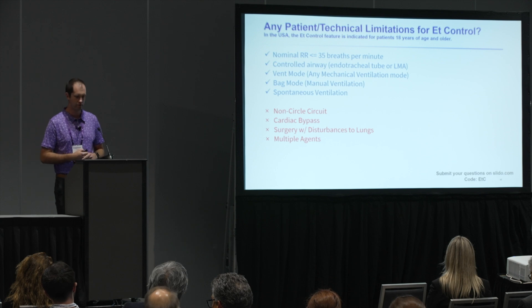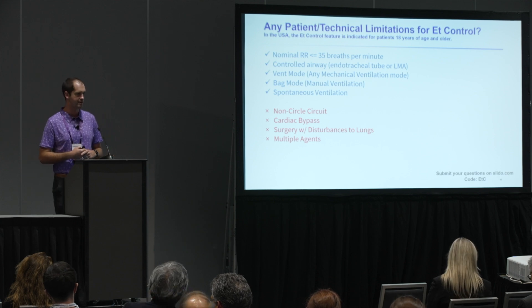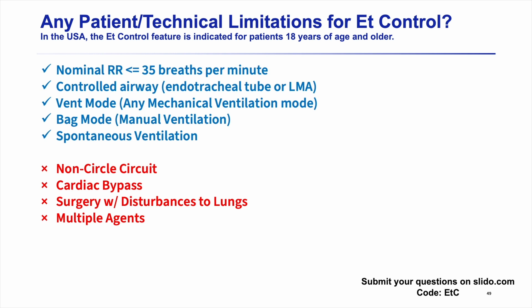What patients can you actually use end-tidal control on? It is indicated for patients 18 years of age or older in the US. You'll need RR less than 35 and a controlled airway. You can use it in any mechanical ventilation mode, in bag mode, or spontaneous ventilation — a pretty wide array of patients. Cases you can't use it on: non-circle circuit, cardiac bypass, surgeries that will have disturbances to the lungs or big leaks in the system — big leaks don't go well with measured end-tidal values. And you cannot use it with multiple agents, just one agent at a time.